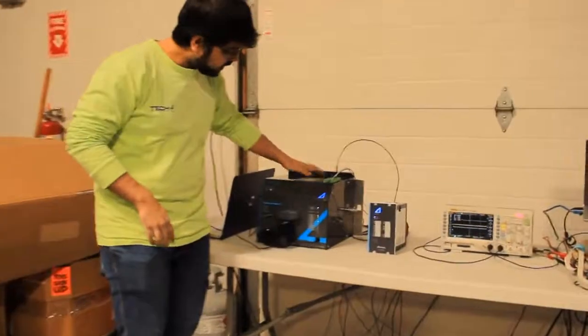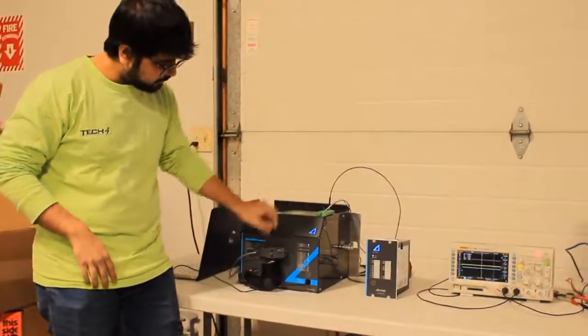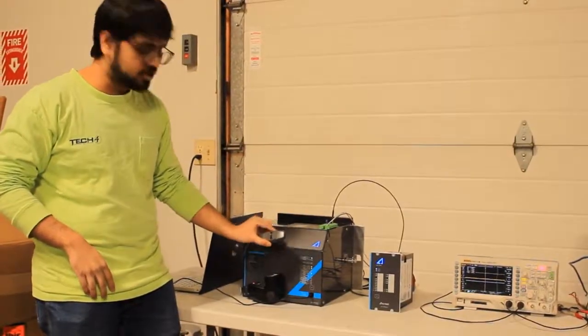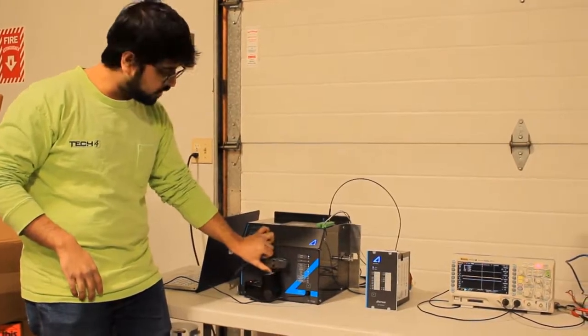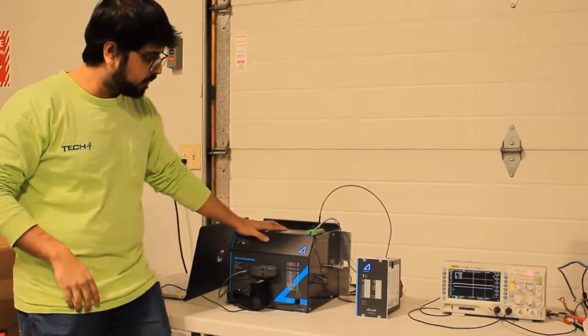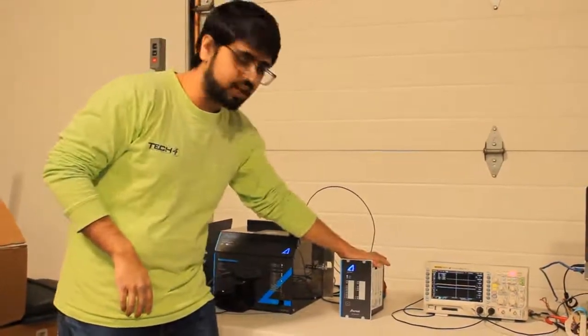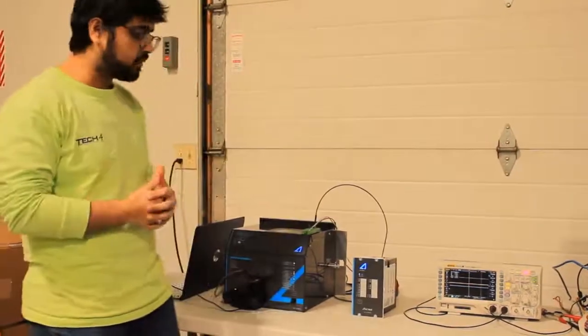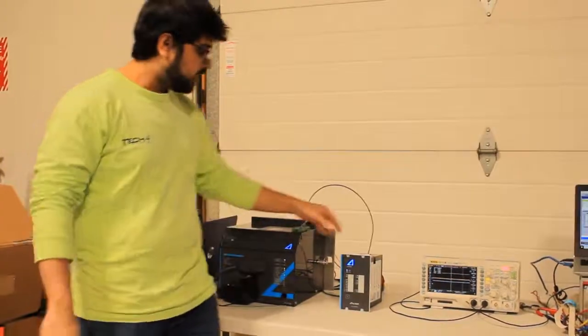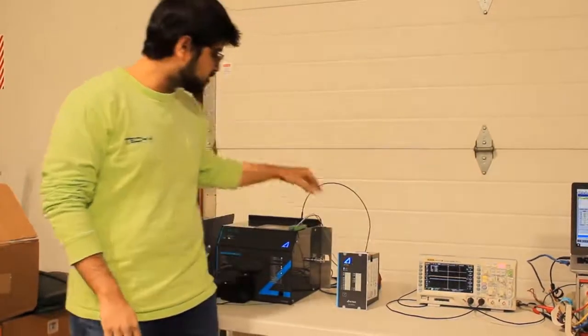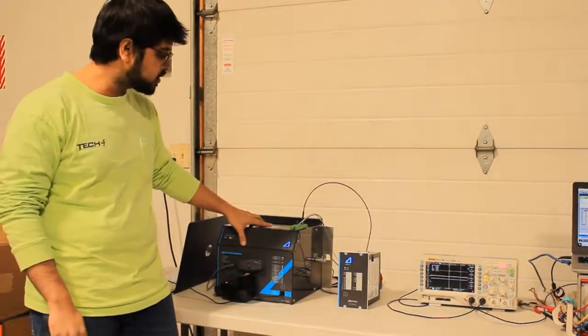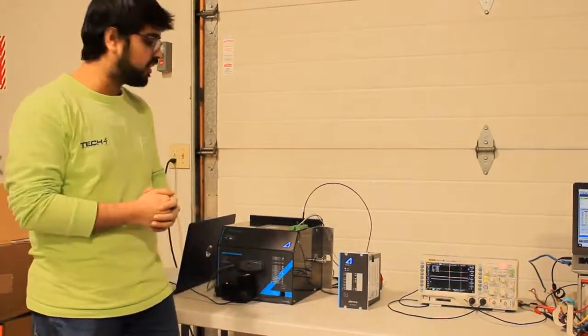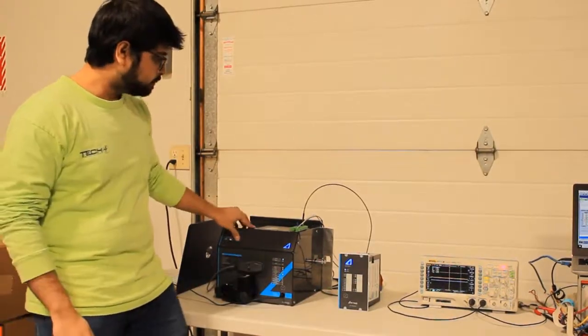The setup we have here, this is the AQ1000. This is the point light sensor. This is what we're going to use to detect the flash. This is the AQ110 arc flash protection relay. It's pretty much the brain of the arc quencher system. It detects the light and current and sends a trip signal to the AQ1000. And all of this takes place under 5 milliseconds.